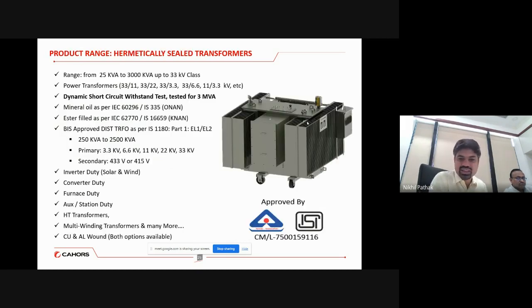Now moving to our core strength of today's session, which is nothing but the hermetically sealed transformers. The only difference is that we cannot offer the transformer beyond 3 MVA capacity, because the corrugation availability is not feasible for capacities beyond 3 MVA due to size and weight constraints. So we are offering minimum 25 kVA to 3 MVA up to 33 kV class. The rest of the configurations remain almost as they are in the case of the non-seal transformer. Now the 3 MVA, which is our highest capacity in this segment, has already been short circuit type tested in CPRI. So the designs are validated in all the ranges down the line. This is also a strength we are delivering, type tested in NABL labs also, and the supply is done in India and the global market.